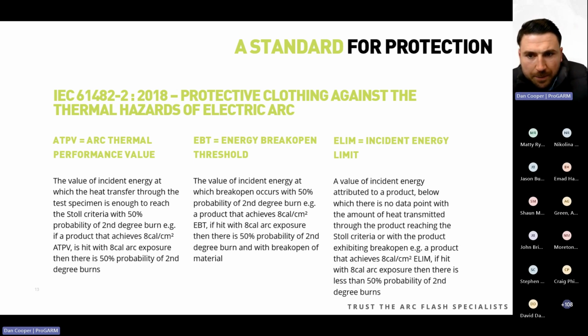One of the key takeaways here is about the ELIM value. ELIM is a new mandatory requirement, and it ultimately means that there's 0% probability of second degree burns, as opposed to the other two. So if a product achieves 8 cal ELIM and is hit with an 8 cal arc exposure, then there is 0 probability of second degree burn. When companies are specifying their cal rating on their risk assessments, we always ask the question as well: is it ATPV or is it 8 cal ELIM? That enables us to make recommendations on the PPE.